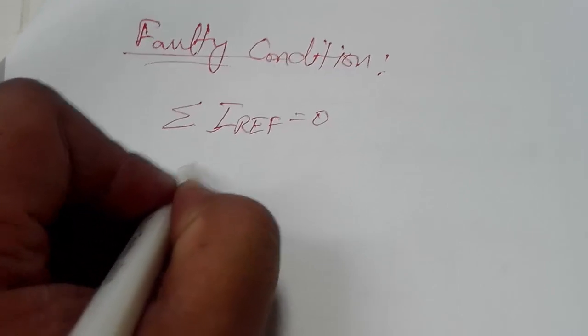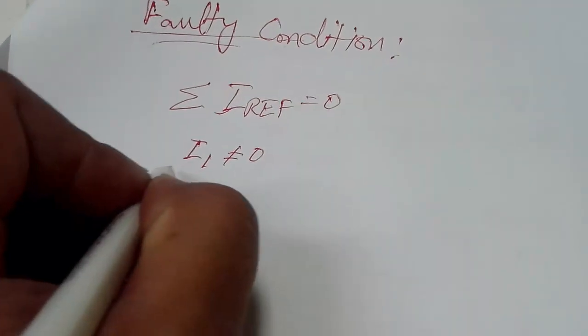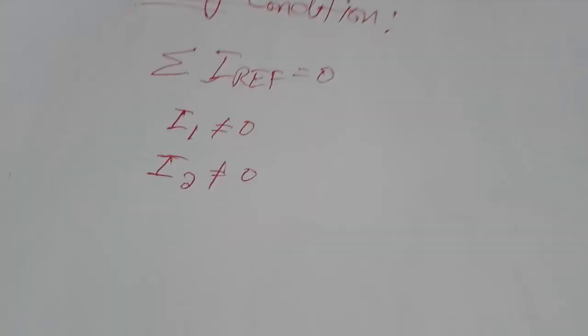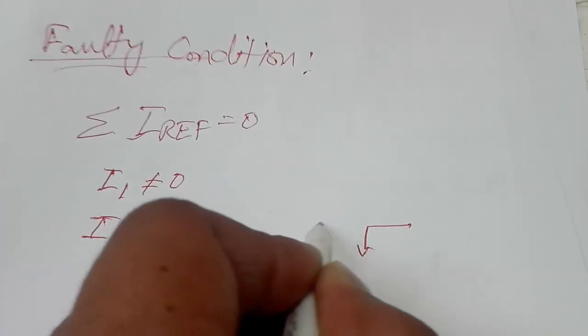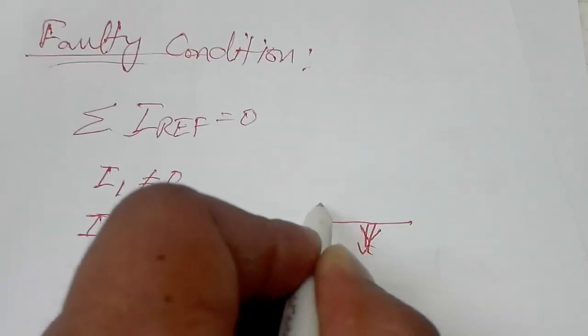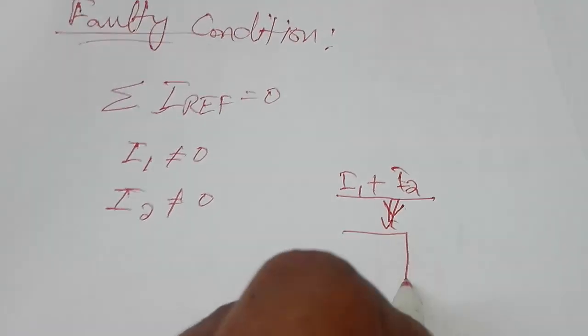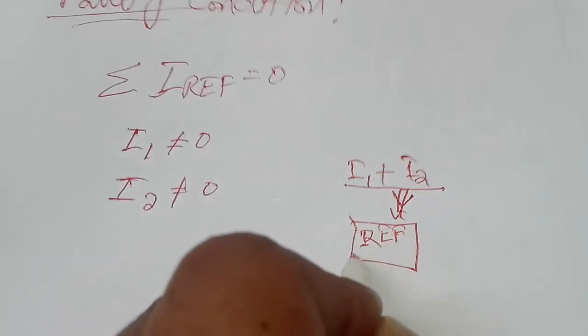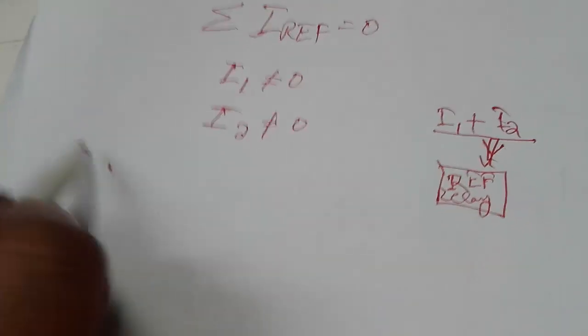In a faulty condition, I1 will not be equal to zero — it will carry some value — and I2 will also not be equal to zero. Both currents flow through the relay and are added up: I1 plus I2. This summation goes into the REF relay, and due to this summation it will reach a set trip value, which we will show during the injection test.